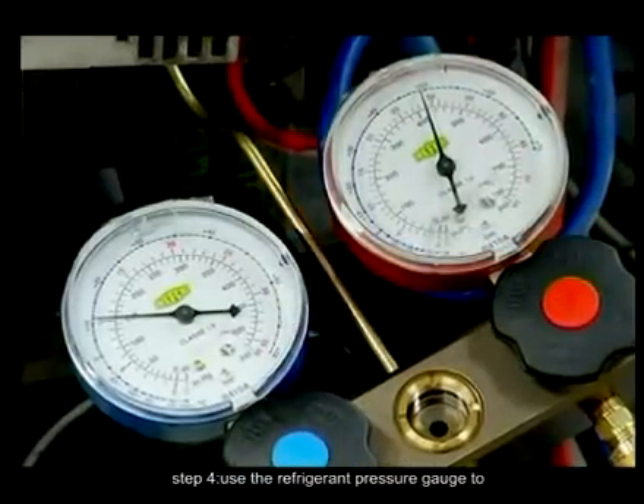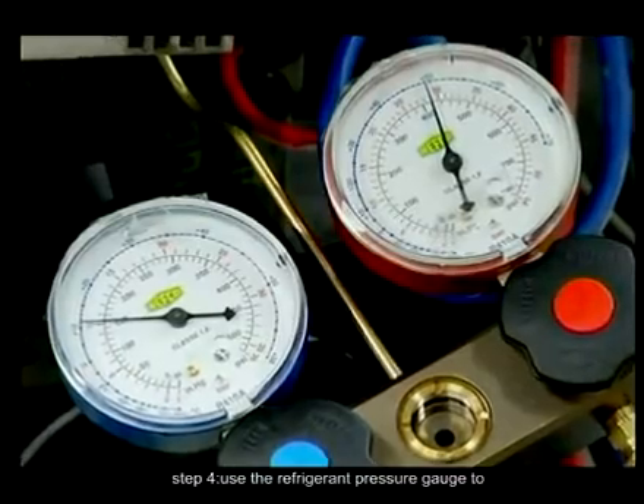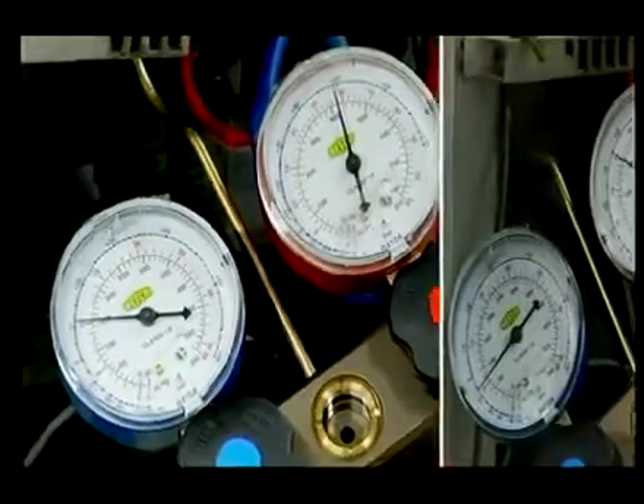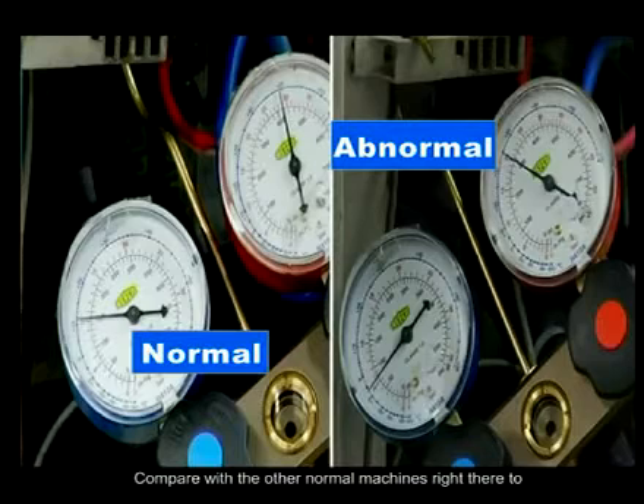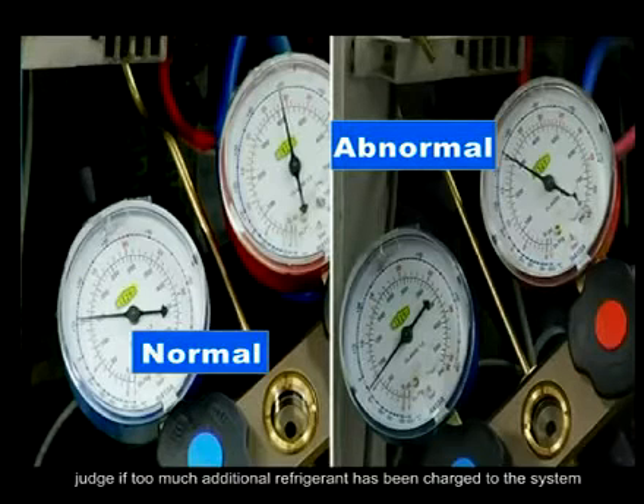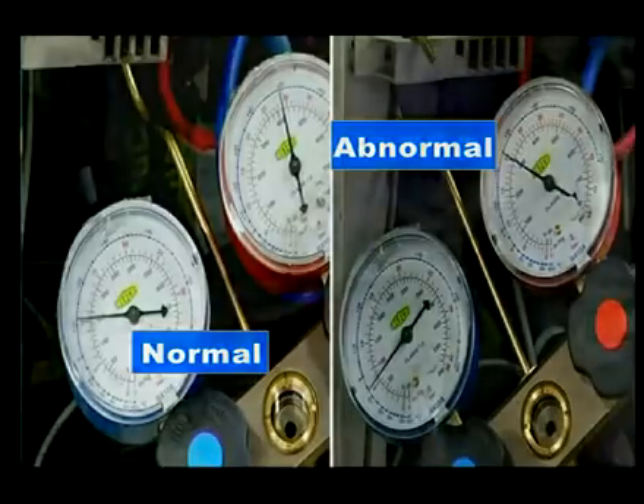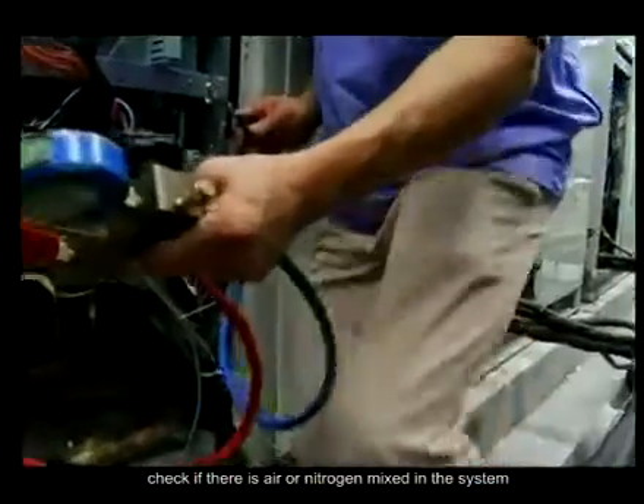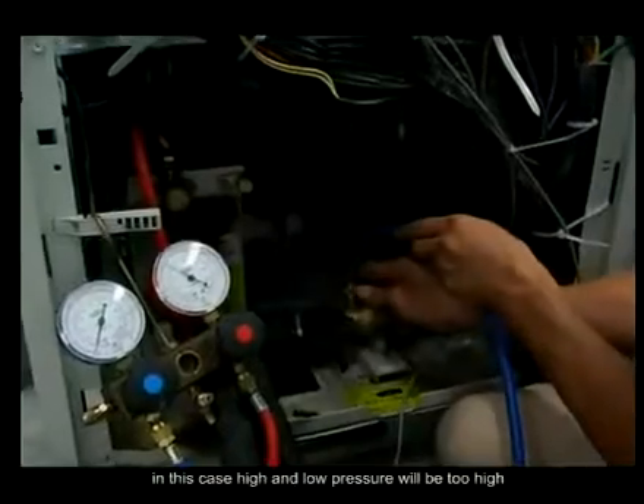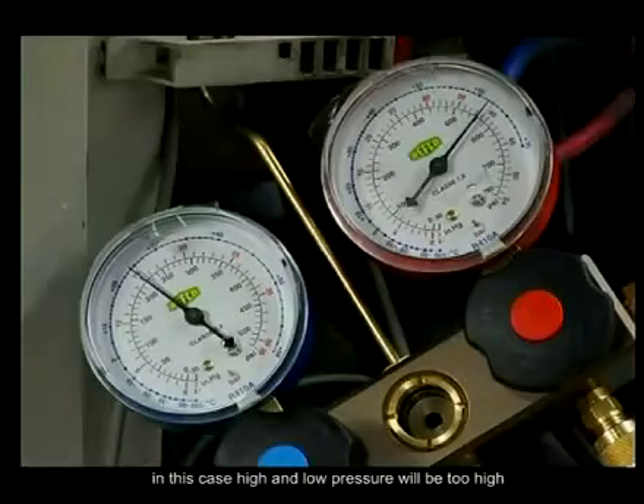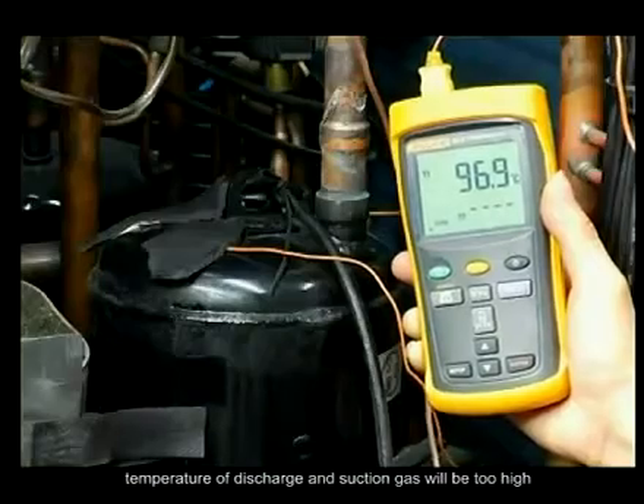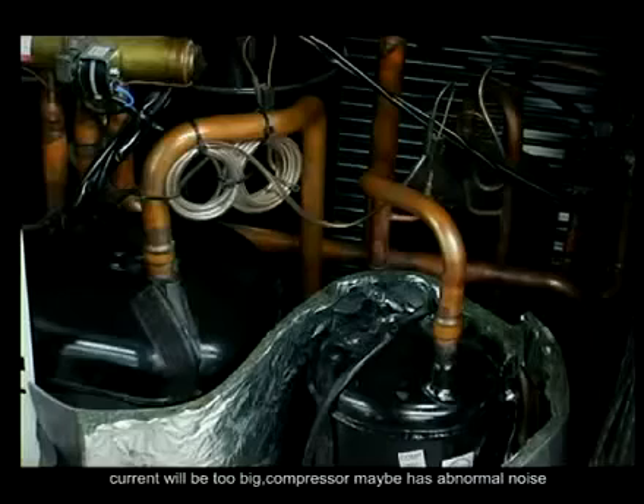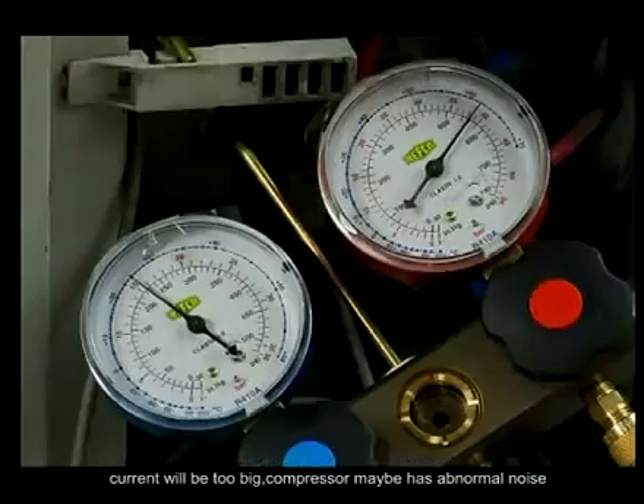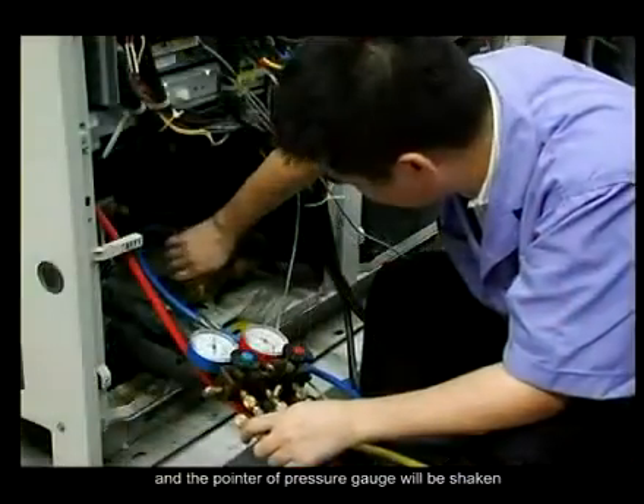Step 4. Use the refrigerant pressure gauge to measure the standby pressure and running pressure of the system. Compare with the other normal machines right there to judge if too much additional refrigerant has been charged to the system. Check if there is air or nitrogen mixed in the system. In this case, high and low pressure will be too high. Temperature of discharge and suction gas will be too high. Current will be too big. The compressor may have abnormal noise, and the pointer of the pressure gauge will shake.